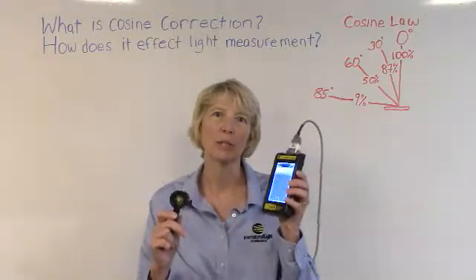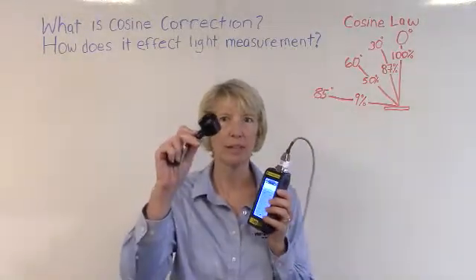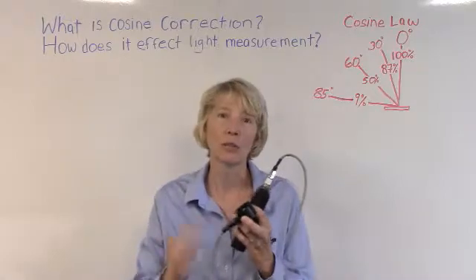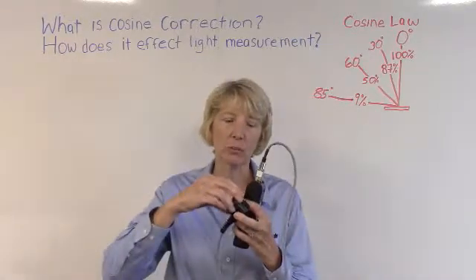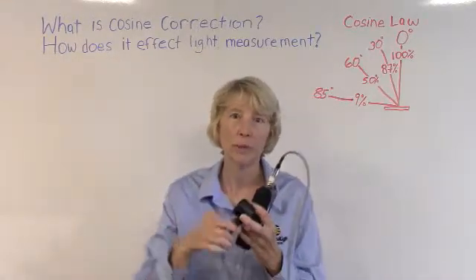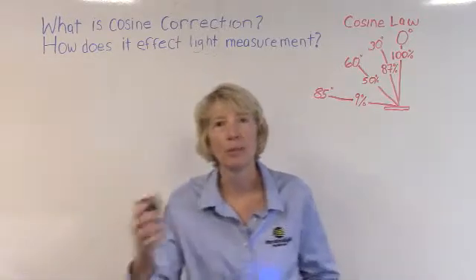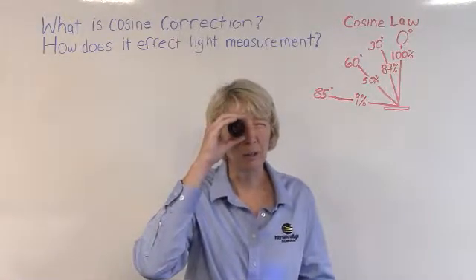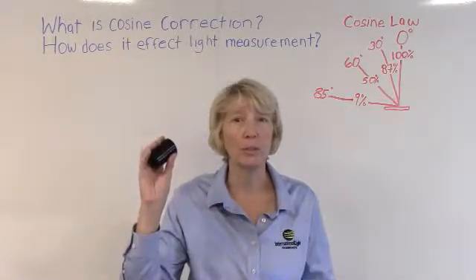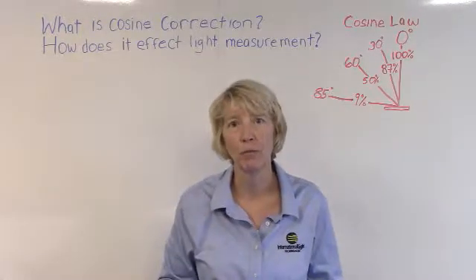Most light measurement systems come with a detector that's recessed inside the housing. Filters and optics are often placed on top of that detector which greatly limit the field of view. This is very similar to placing a cone in front of your eye which would eliminate your peripheral vision, basically giving you a very narrow field of view.